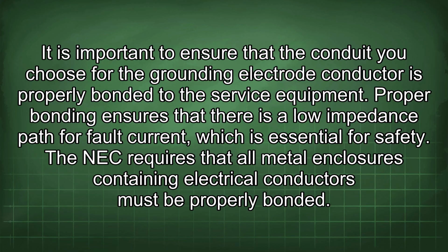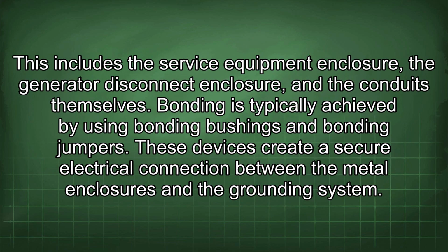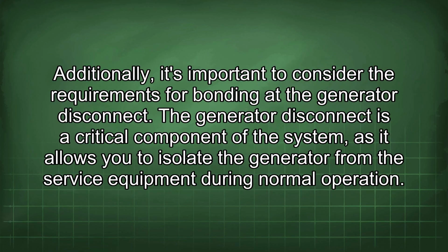The NEC requires that all metal enclosures containing electrical conductors must be properly bonded. This includes the service equipment enclosure, the generator disconnect enclosure, and the conduits themselves. Bonding is typically achieved by using bonding bushings and bonding jumpers. These devices create a secure electrical connection between the metal enclosures and the grounding system. Additionally, it's important to consider the requirements for bonding at the generator disconnect.